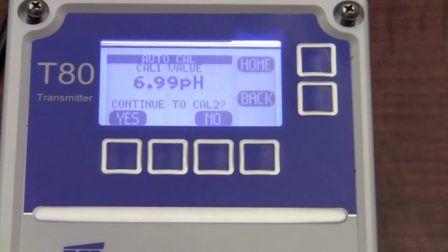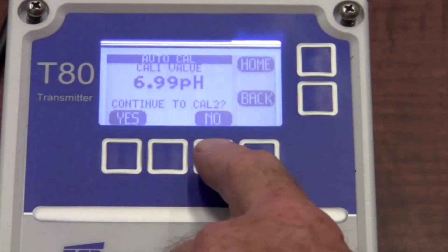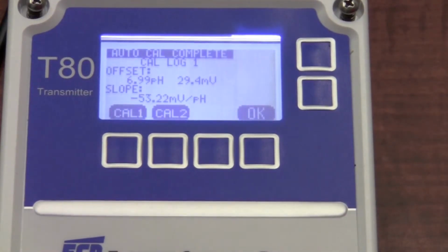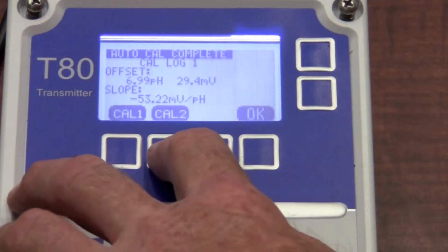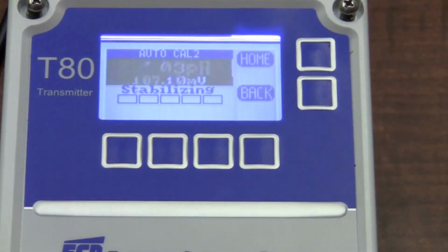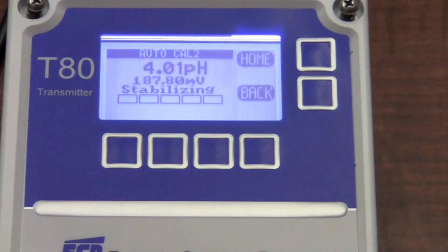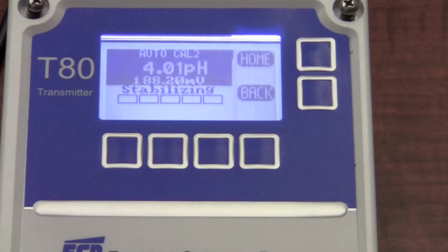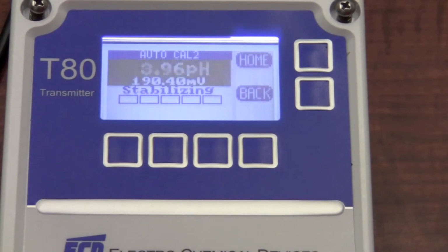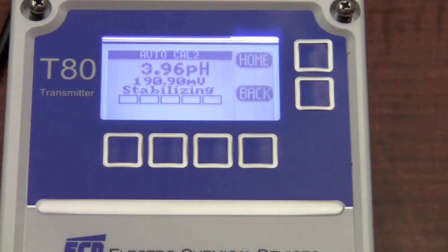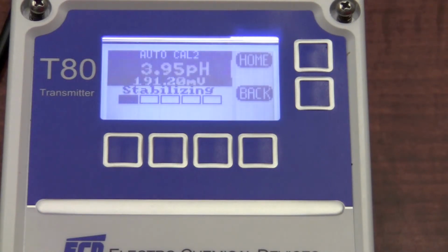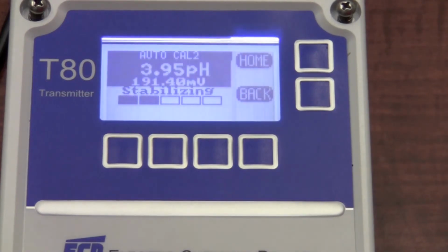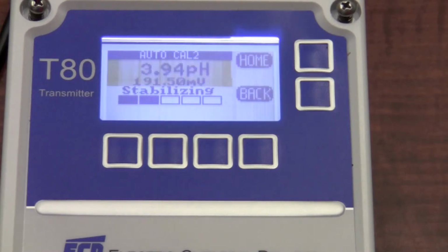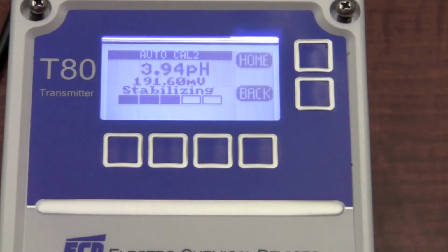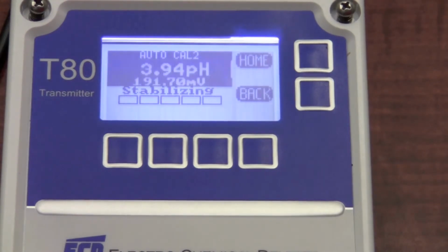With the first calibration point completed, I'm going to continue on to cal number 2. For cal number 2, I'm going to use a pH buffer solution of 4. Once again, the transmitter looks for stabilization in the reading. An ideal slope on a pH transmitter is 59.1 millivolts per pH count. Right below the pH reading, you also get a raw millivolt value. Once the stabilization is completed, we'll return back to the operate mode.